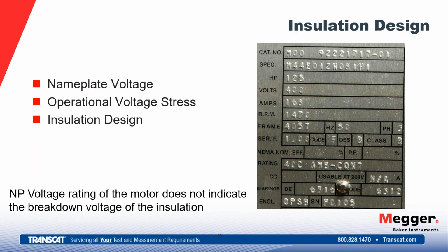So here we have a picture of a nameplate. Nameplate voltage is being displayed here. This particular motor, its nameplate's at 400 volts. So it's built to handle and designed to operate at full load with 400 volts of applied voltage there. The nameplate rating of that motor does not necessarily indicate the breakdown voltage of that insulation. So the voltage rating of the motor is not concerned with the breakdown voltage of the insulation. The breakdown voltage is the voltage above which the insulation breaks down electrically.